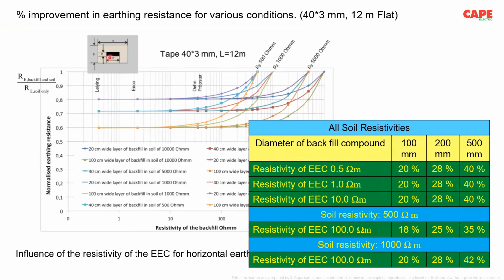A horizontal conductor you can see here with a tape. Three or four different manufacturers make earth enhancing compound, and you can see the resistivities which they are offering. For example, one of the makes is something about 1 or 2 ohm meter. With the different resistivities, the same results are published, and I just put it on the table.